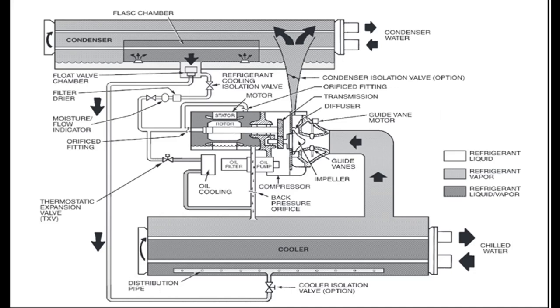Oil is charged into the lubrication system through a hand valve. Two side glasses in the oil reservoir permit oil level observation. Normal oil level is between the middle of the upper side glass and the top of the lower side glass when the compressor is shut down. During operation, the oil level should be visible in at least one of the two side glasses. Oil sump temperature is displayed on the CVC/iCVC chiller visual controller default screen; during compressor operation, the oil sump temperature ranges between 125–150°F (52–66°C).